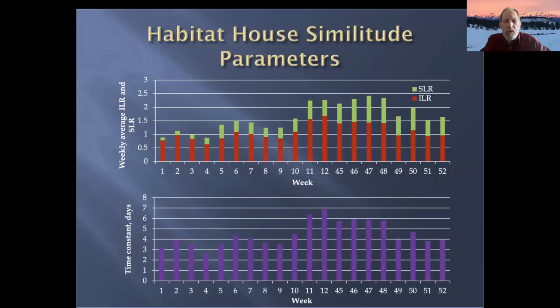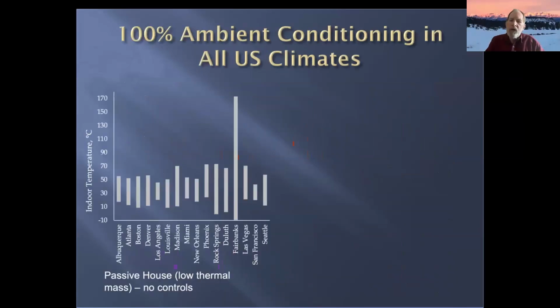Thermal time constant depends on outdoor temperature, and so it ranges from about 2.5 to 7 over the heating season. So I had a question during the registration period about more challenging climates. And in the next couple of slides, I want to show performance of a building that's 100% ambient conditioned in every climate zone in the US. And we're even including Fairbanks, Alaska, where we have almost 3 months of very little sun.